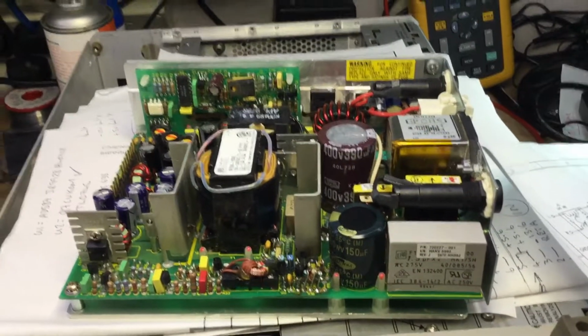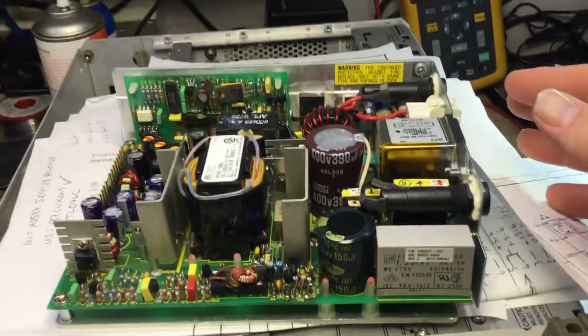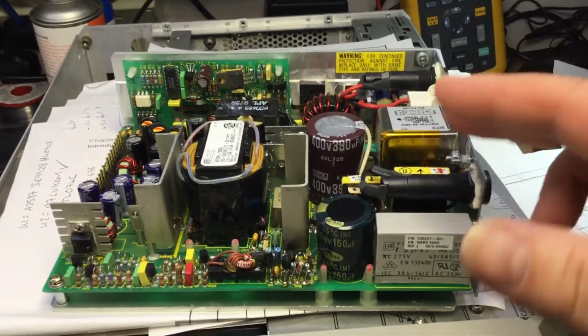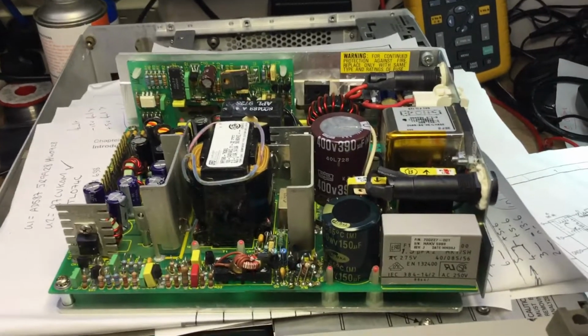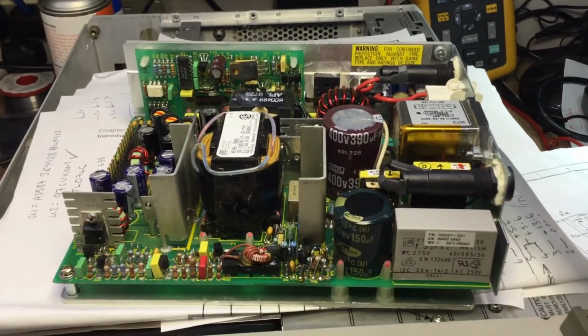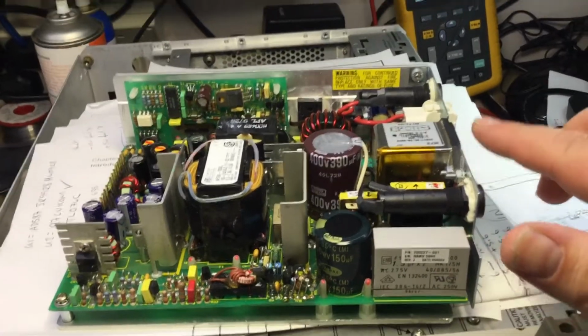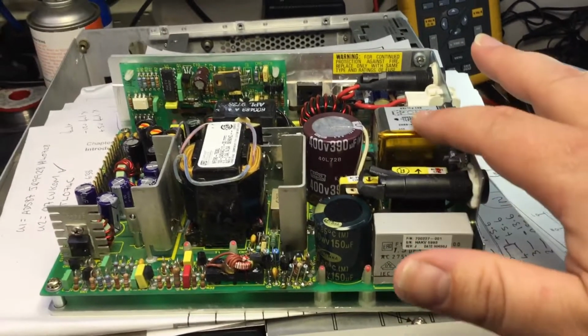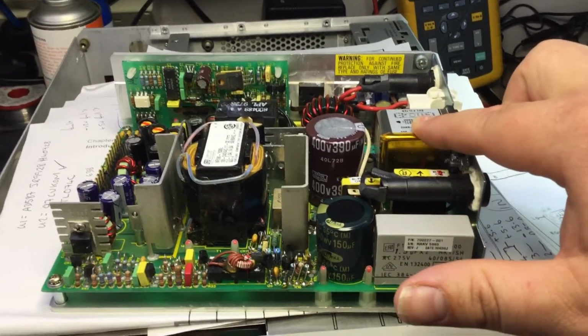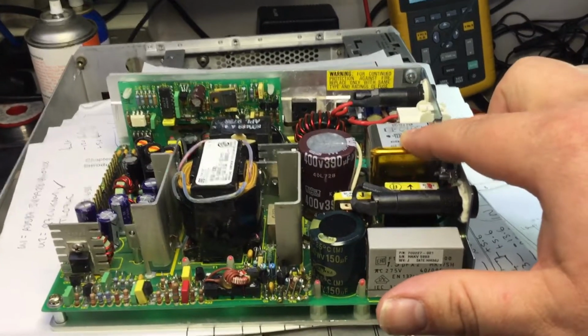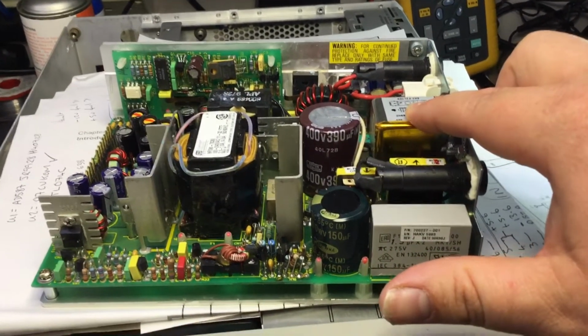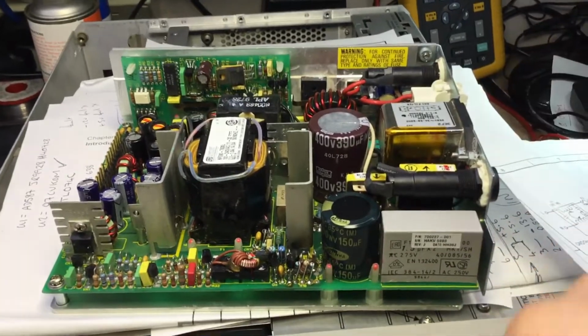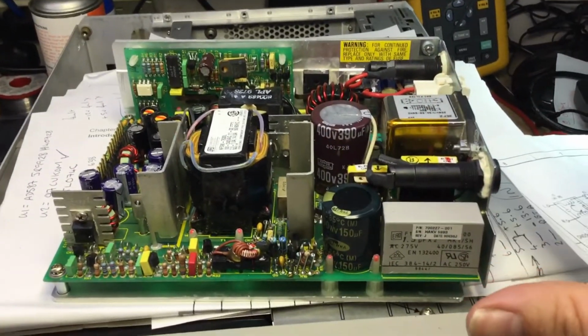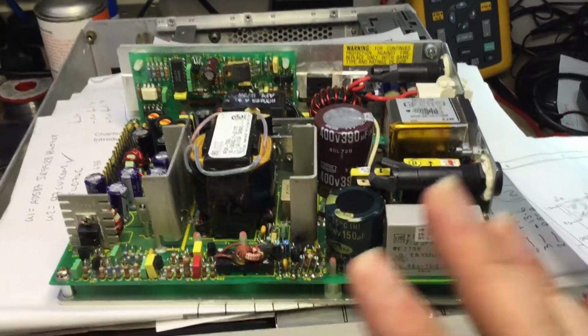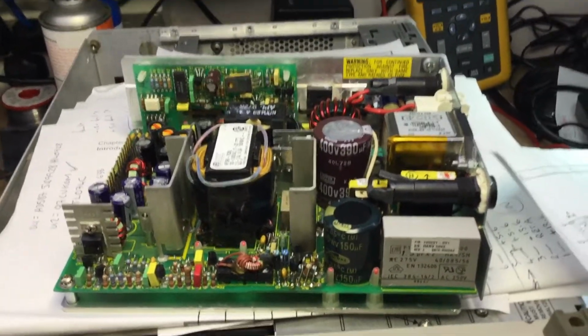It's my recommendation that while doing any repairs and testing, use the DC input first to try and diagnose or sort problems out on the main switching side before you introduce mains, because mains input is very unforgiving. In this country, the UK, we have 13 amps at 240 volts AC, and it doesn't give you much room for error. If there's any problem, you're just going to get fizz, bang, and bush - that's it, a cloud of smoke and components destroyed, all sorts of problems.